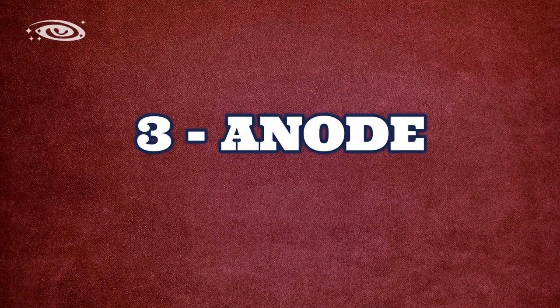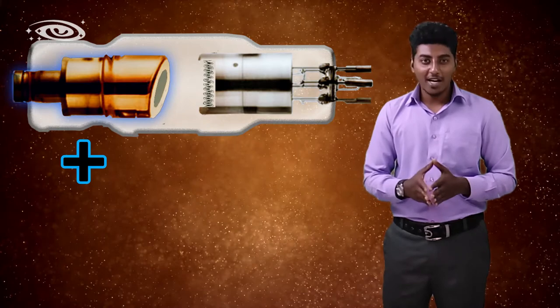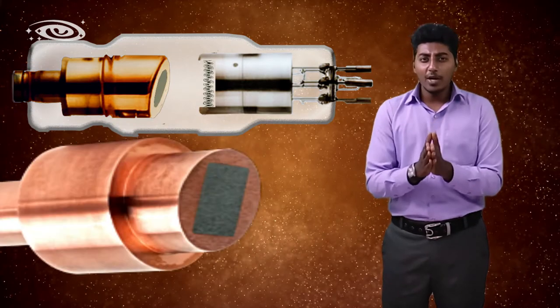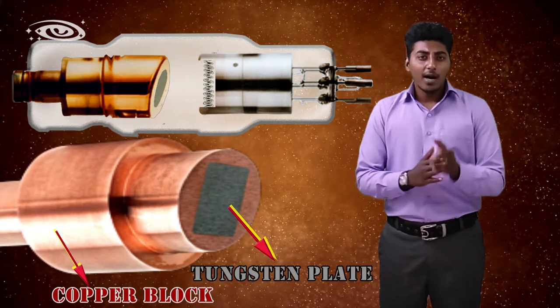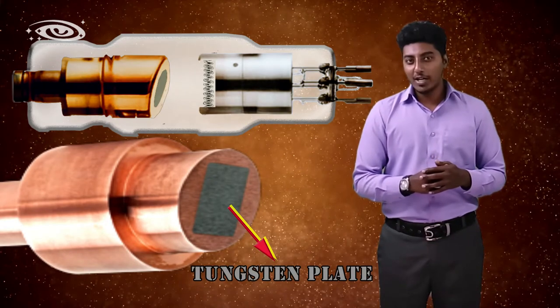At last we will see about the anode. Anode is the positive side of the x-ray tube and is made up of two major parts: the tungsten plate and copper block. The tungsten plate is used as a target metal to produce efficient x-rays.